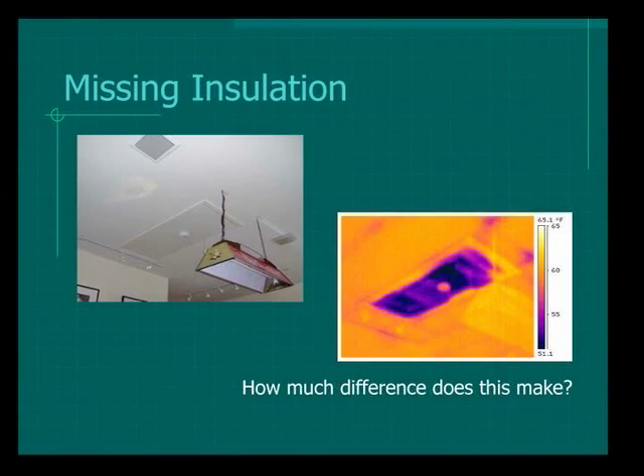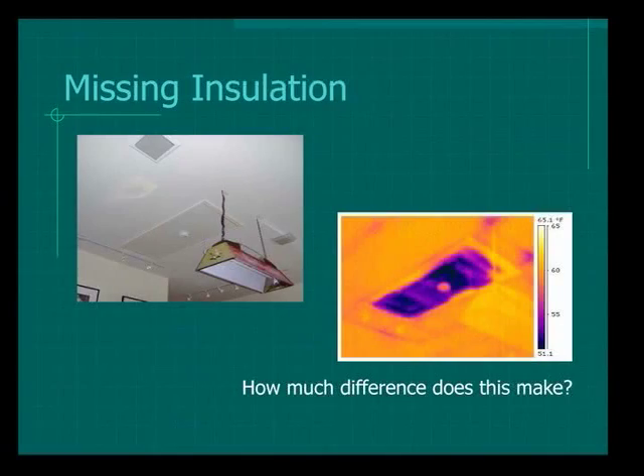John gave you a picture like this, kind of a trivia question. This is a pull-down attic hatch with no insulation, so it's half-inch plywood. Let's give it the benefit of the doubt and call it R1, though it's probably a bit less. Let's say the surrounding ceiling is R38, a code insulation value, perfectly installed with no deficiencies. So R38 for the whole roof and R1 for that attic hatch, which is 2 foot by 5 foot, 10 square feet, in a 1,500 square foot attic.